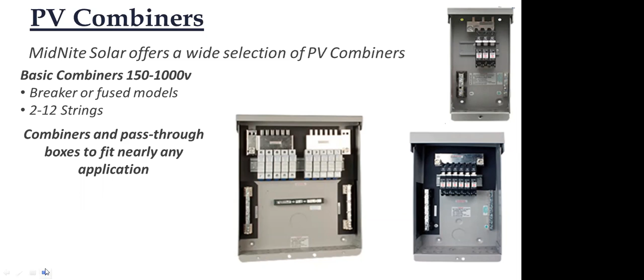One of the problems with a lot of these charge controllers, be it MidNite's or anybody's, is you've got such a high voltage on the input. If there's a catastrophic internal failure, there's potential for the output to go to an uncontrolled high voltage. We haven't seen that in the Classic line, or in the Hawke's Bay, but we understand how it could happen with the right combination of component failures.